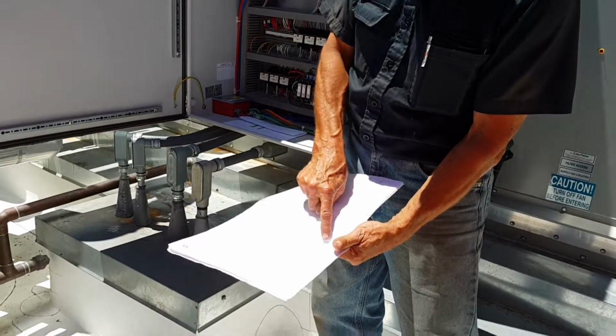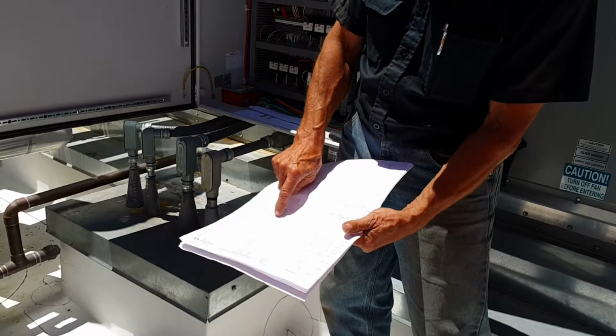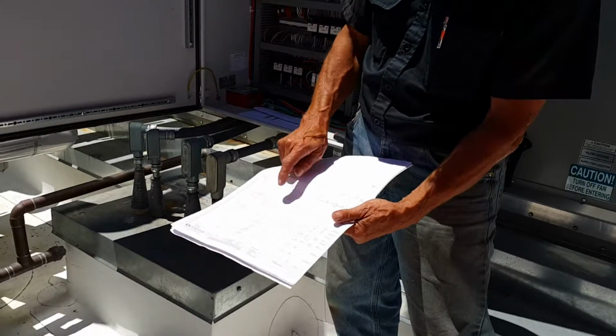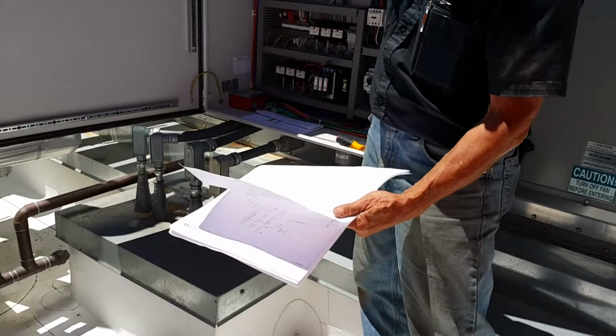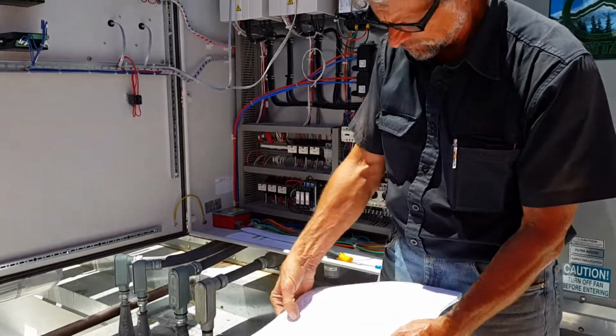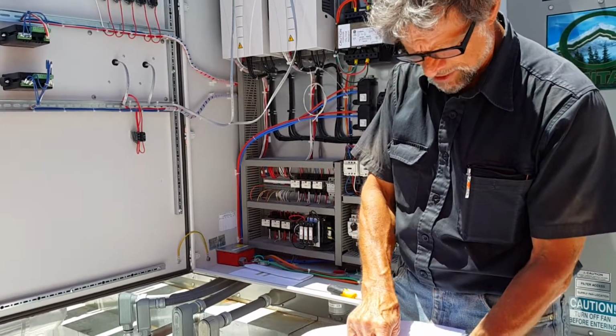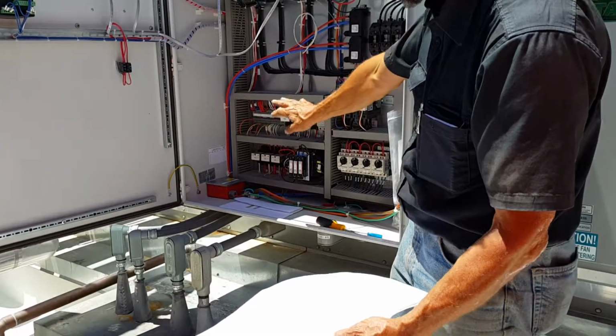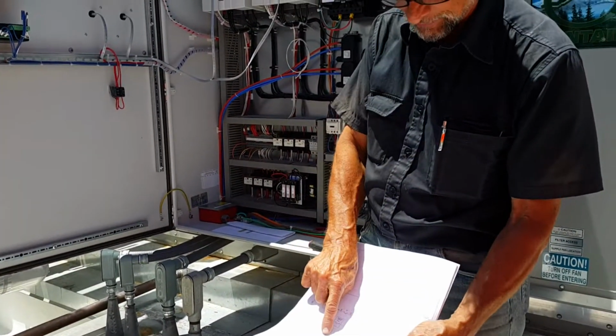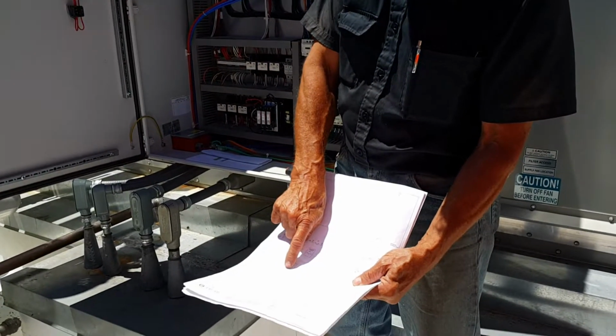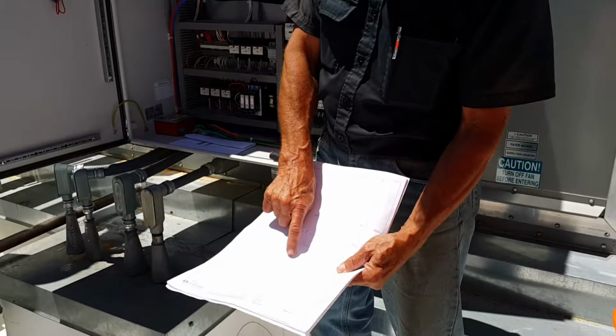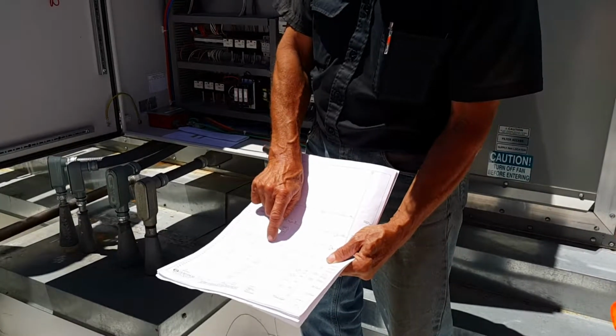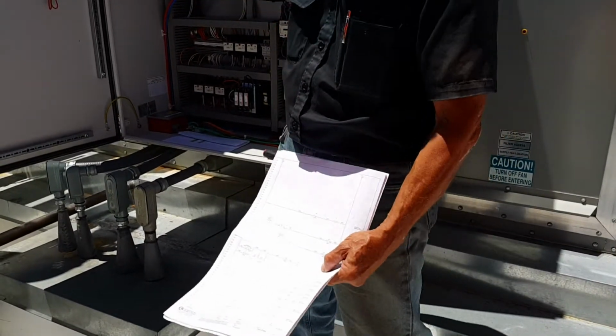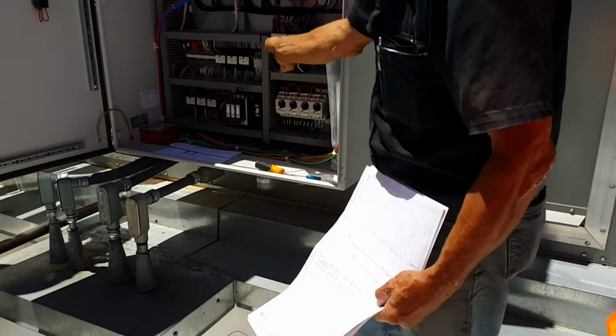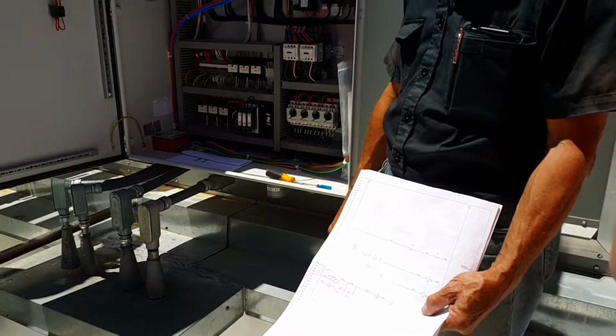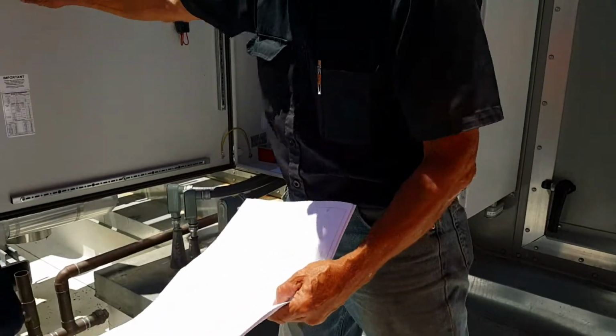Notice how it goes down two parallel lines. There's contacts in between. These contacts are driven by the alarms in here. So if I select this drive, it's running this contactor output to the motors, and that drive goes into alarm. Switch here and open here. So this contact line will now come down through here. Even though I've selected drive 1, it'll pull in the contactor for drive 2. And that will happen automatically.